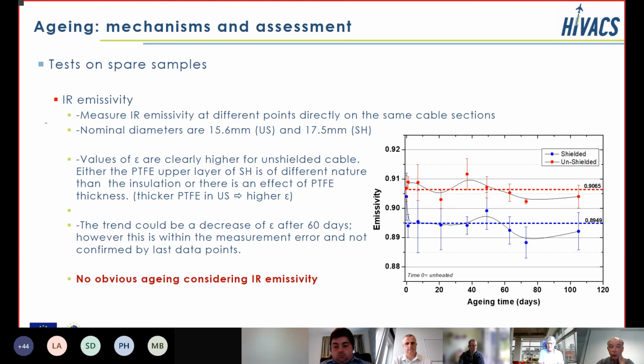The measurements also consisted of infrared emissivity. Infrared emissivity is important for the thermal modeling. The coefficient of emissivity enters into the thermal modeling of the cables, and we could see a clear difference in the coefficient between shielded and unshielded cables. That seems to be probably linked to the thickness of the outer Teflon layer of the cable. But except for the differences that are due to the construction, there is no evolution as a function of aging time.